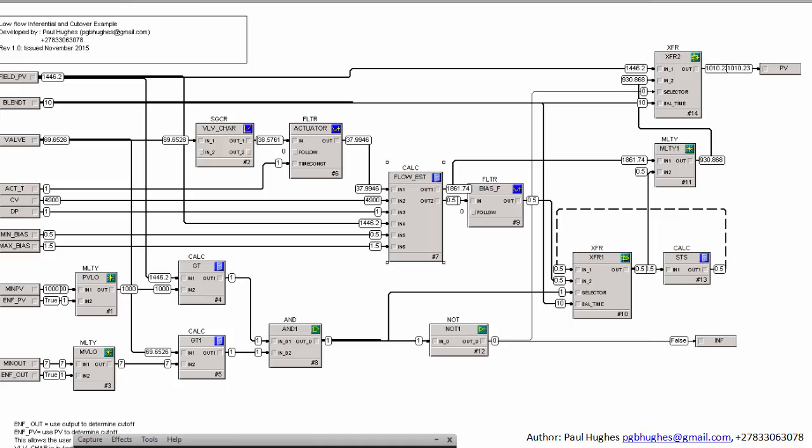So you'll notice as we're running, this value is going to toggle a bit because we're moving over the regions where the reading in the field is unreliable, because we specified a minimum PV of 1000, which we know is too low, because typically it's going to be below 1500. So that's this block.